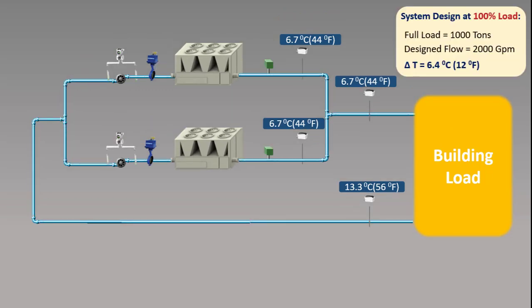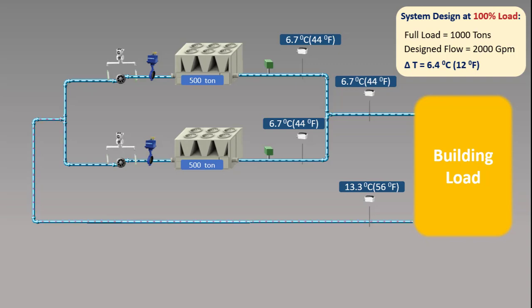Now let's consider that this system has a full load of 1000 tons with a design flow of 2000 GPM and a design delta T of 6.4°C (12°F). At full load, each chiller is supplying 500 tons of cooling capacity and each pump is supplying 1000 GPM, so total flow is 2000 GPM to the building and delta T is 12°F or 6.4°C. Chilled water systems run at designed full load for a very small amount of time — usually about 1% of their lifetime.